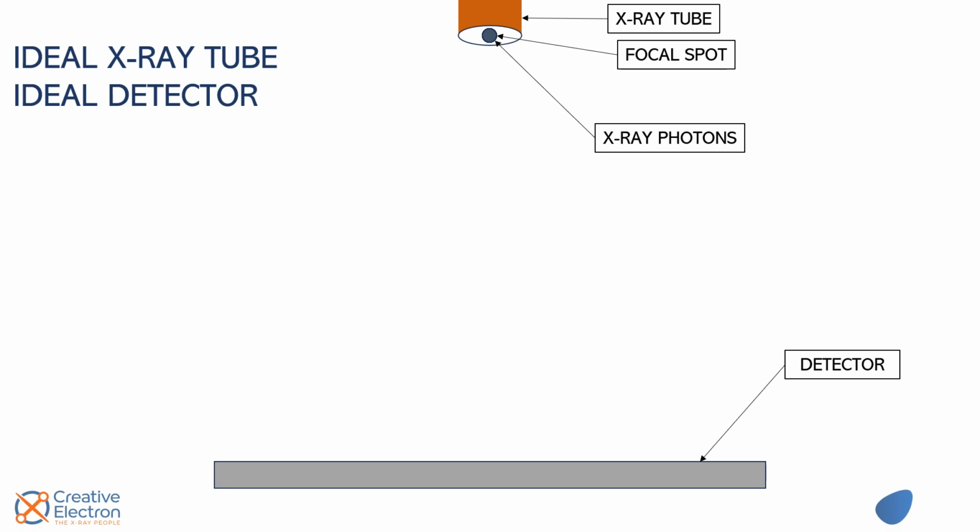Now, how does an ideal X-ray tube work? We have this really fancy animation here to show you. These round gray things are the X-ray photons. They are generated by free electrons in the target, and they exit the tube at this location we're calling the focal spot. The idea of this animation is to show you that every single X-ray photon in an ideal X-ray tube does not intersect the track of another X-ray photon.